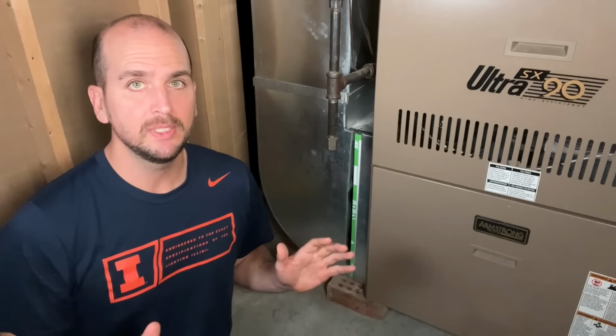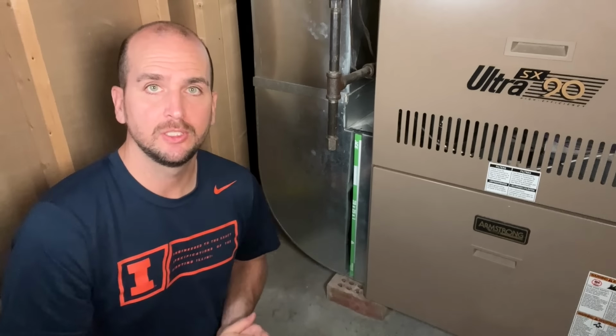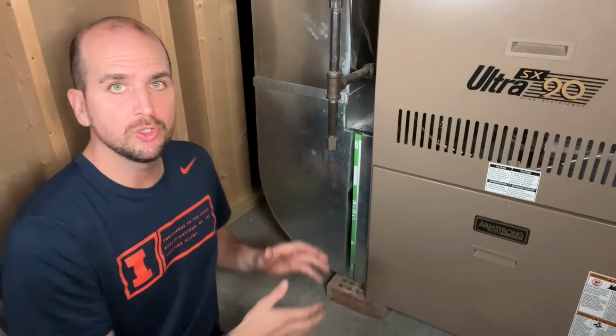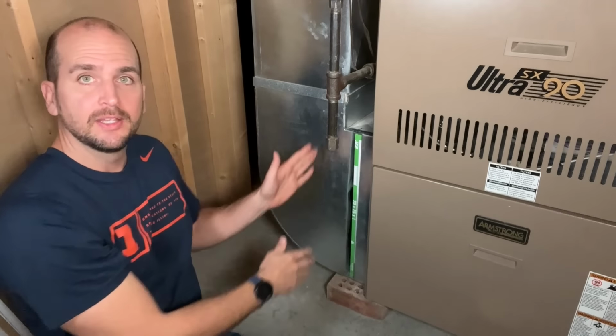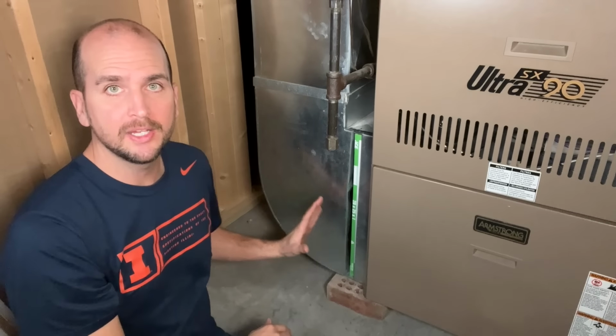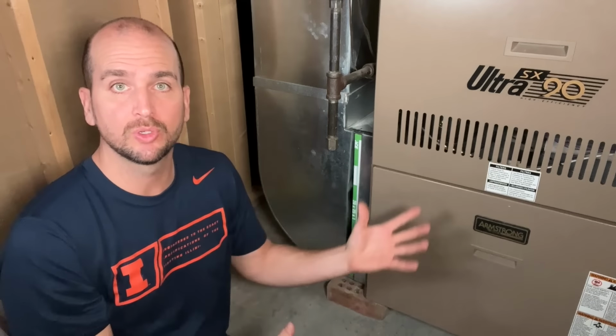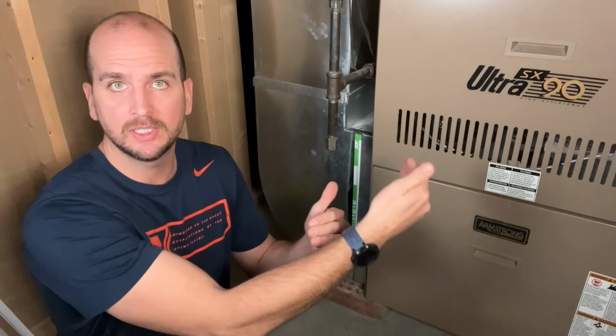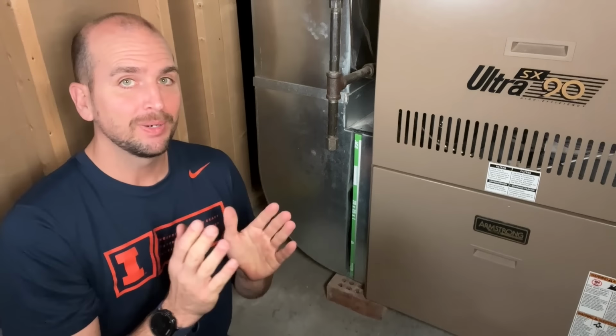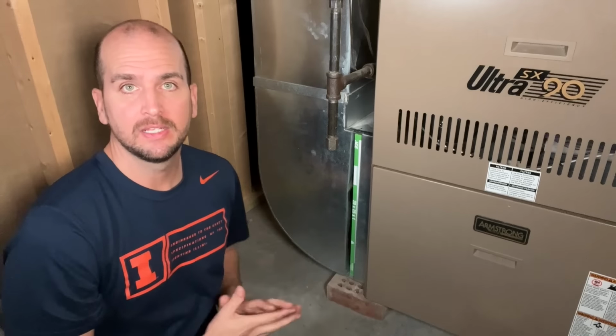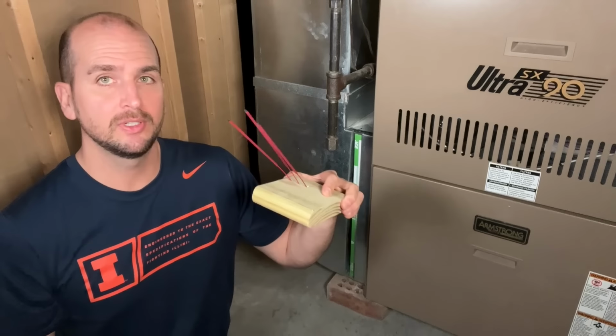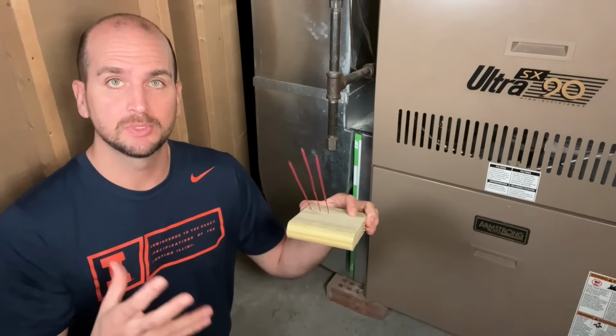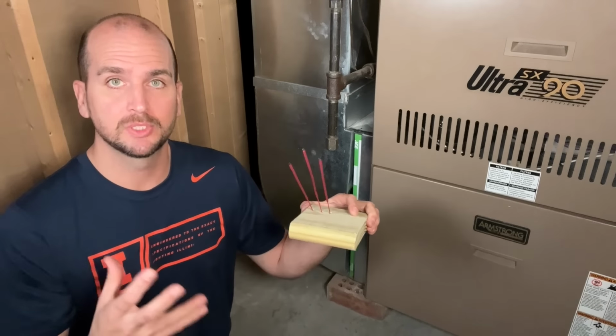Today I want to show you how to quickly correct an issue that is extremely common in most homes. If you have a central air system or a furnace with a return duct that goes through a filter before the air gets conditioned, whether heated or cooled, the problem is right at the furnace filter slot. I'm going to demonstrate this with some incense and smoke to show the path of airflow and how to correct it.